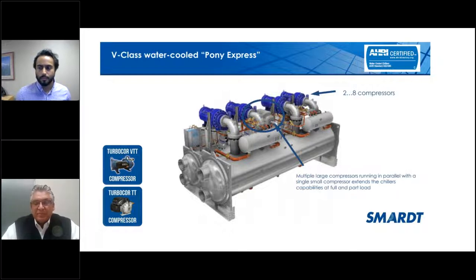You can maybe just respond by raising your hand, but as we all know, as we get into large tonnage applications, the ability to have cooling during the shoulder seasons creates an issue, especially on minimum load capabilities of the machine. Any high efficiency, high lift machine will have difficulties at low load and minimum load during shoulder seasons. In the past, you would traditionally add a shoulder chiller, a pony chiller if you will, or a side stream chiller to the existing chilled water loop. In this case, Smardt has taken that next step up and put that small compressor on the existing chiller. So now we even have a low load capability and do not have to add a second machine or a small pony machine. It's a really good application. It's a great approach, and efficiencies are obviously very good based on the tube surface for the same amount of tonnage in that compressor.